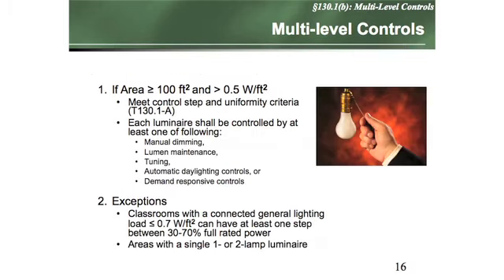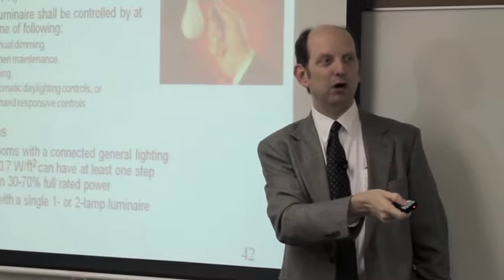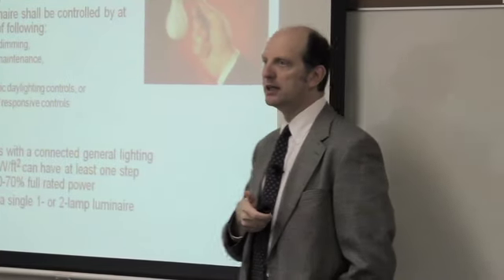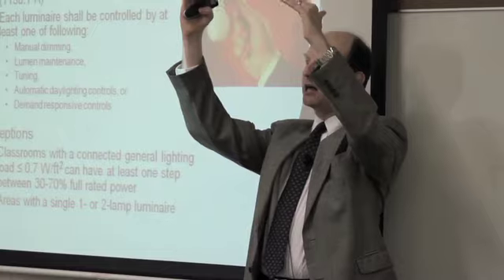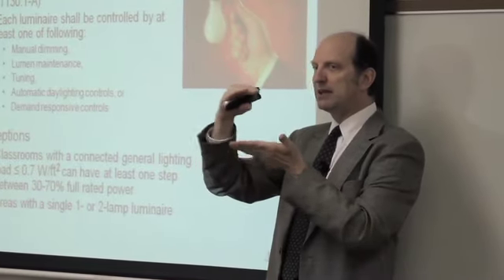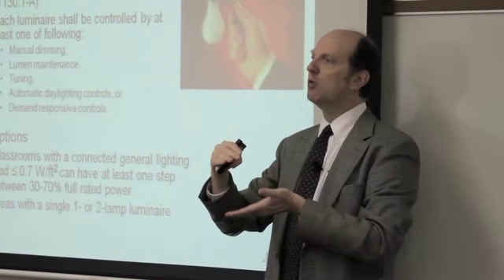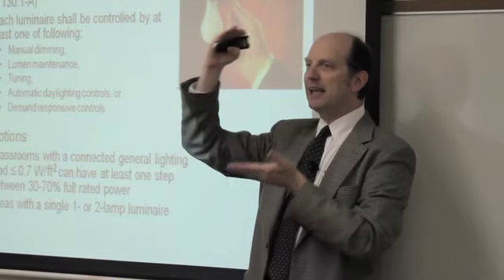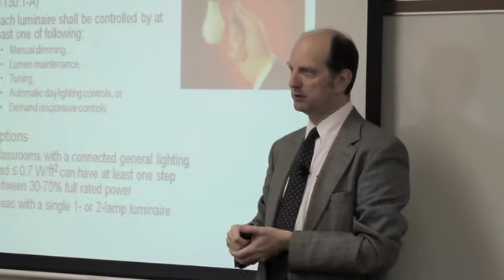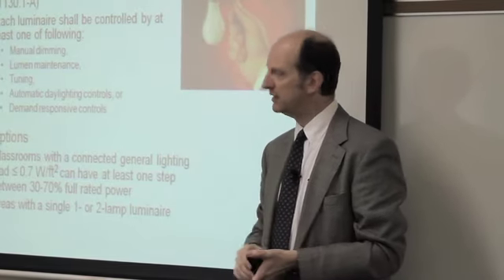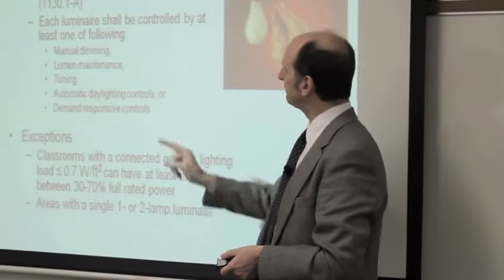This is probably the biggest change in the code and the one most people are shook up by. California has been the land of bi-level lighting for a long time. The reason we have not 1 but 2 switches on the wall is because we want to go not just from 100% to off, there's got to be some intermediate level. What is the intermediate level today? Any level you want between 30 and 70%. Nice and easy. They're going to change that.